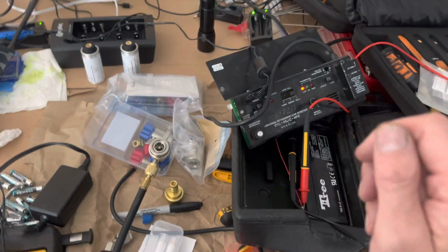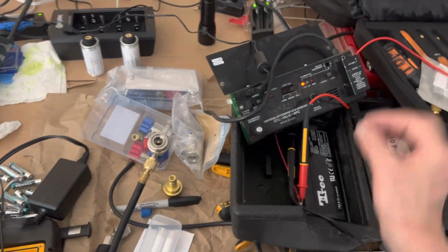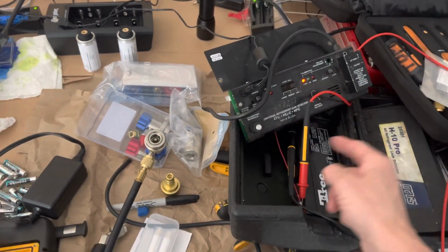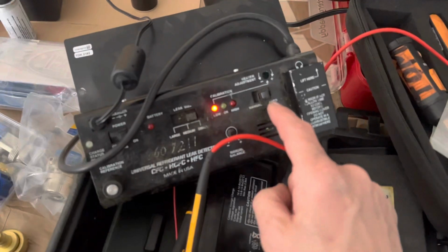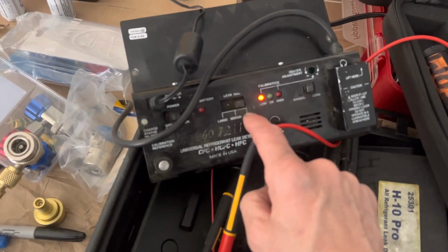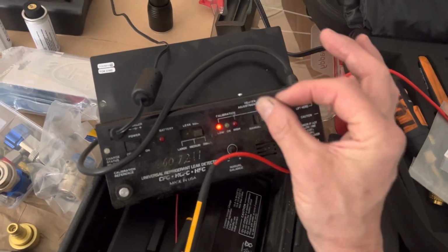But you burn out the sensor faster. You shorten its life. But when you're in an area and you really want to find a very small leak, temporarily you go through the recalibration process. I have it in auto. I have it on small leak, and then you go through the recalibration process. That's all handled here.